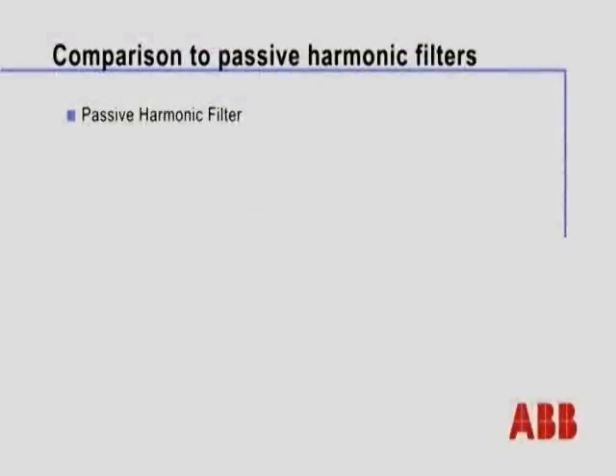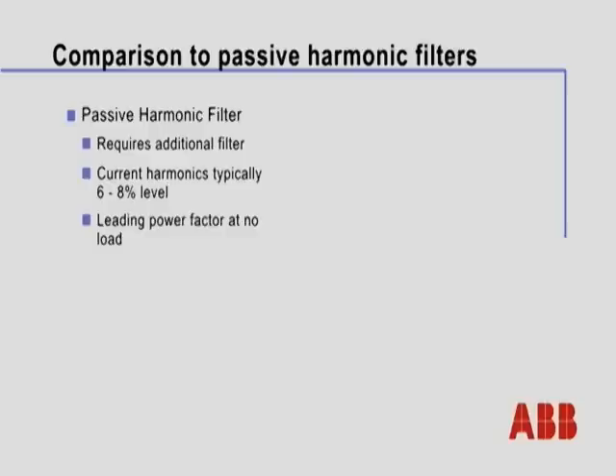Passive filter solutions require additional filters, so that means going outside the box, if you will. More real estate, more hardware to wire up. Secondly, the level of harmonic mitigation that can be provided is really only in the 6 to 8% range. Leading power factor can also be an issue with a passive filter solution, as will voltage drop because of the filter being placed ahead of the drive. With voltage drop, you may not get full voltage out to the motor.